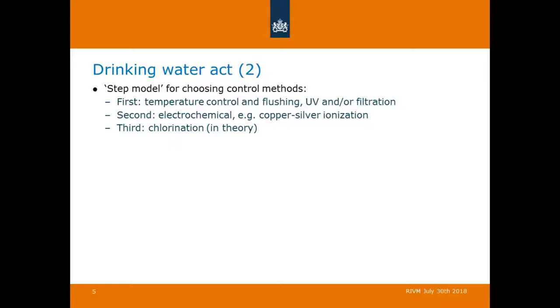The first step is you can use temperature control and flushing and heat disinfection, or you can use an ultraviolet or filtration system. If the water management company can prove that this is not sufficient enough, you can go to the second step, that's electrochemical, for example copper silver ionization. And in theory, we can go to the third step, the chlorination of the drinking water, but to my knowledge, that has never been approved by the inspectorate.